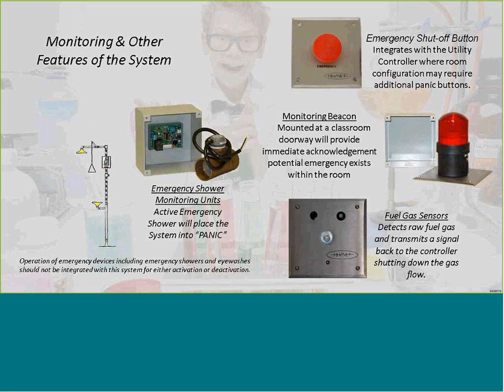And of course, the best way to protect your building is to have a fuel gas sensor. A fuel gas sensor monitors 24/7, 365 days a year. It does not shut off. It's constantly on, so that if a gas turret is left open, or let's say you get a gas pipe that leaks, at least in the classroom itself, it will sense that gas and shut the system down. The fuel gas sensor will send a supervisory signal out to the administrators, but as long as that sensor is sensing gas, the system cannot be reactivated until the area is cleared and the sensor no longer senses fuel in the area.